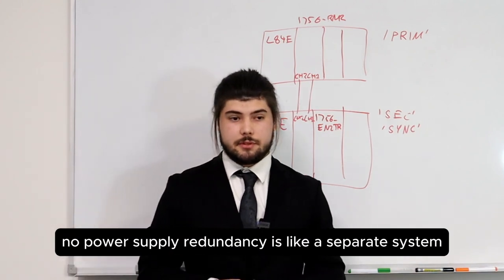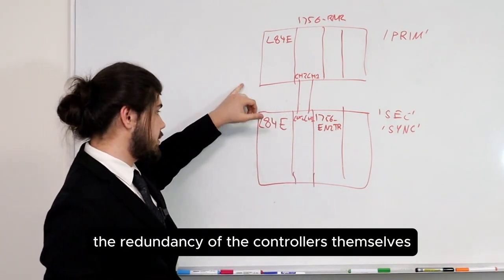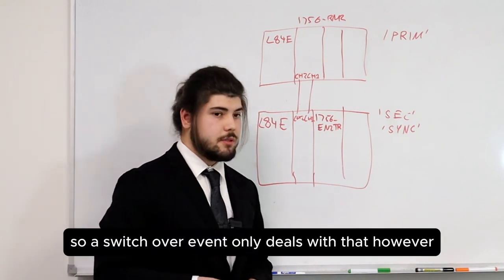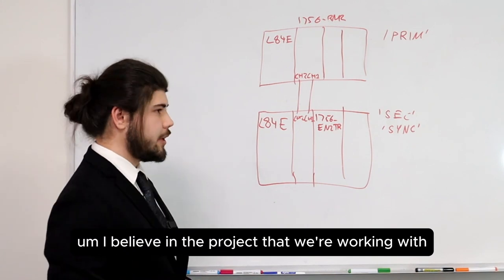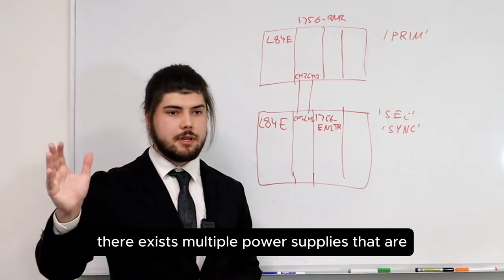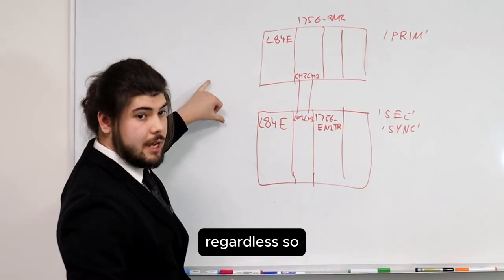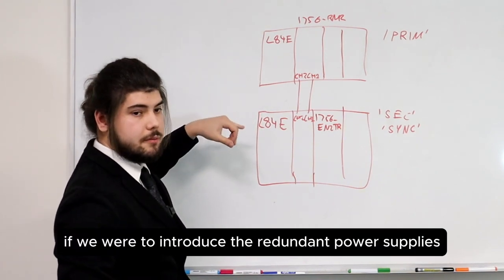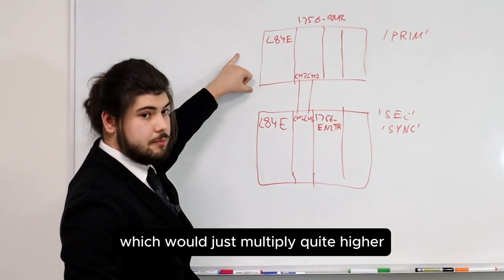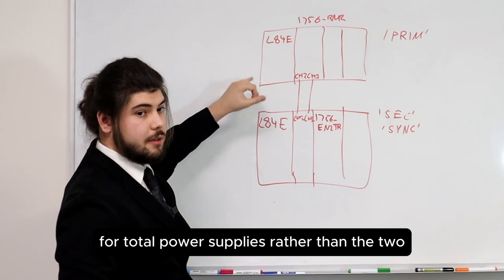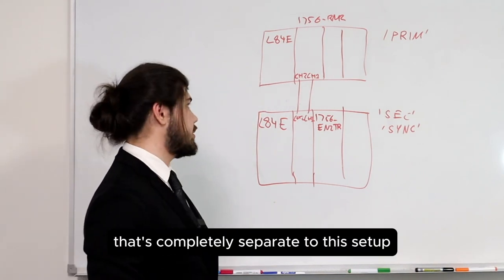Power supply redundancy is a separate system with a separate manual. This presentation is just dealing with redundancy of the controllers themselves. A switchover event only deals with that. In the project we're working with, there exist multiple power supplies supplying both PLCs and both racks separately. If redundant power supplies were introduced, you'd have two power supplies per PLC — four total rather than the two which already exist and are in themselves redundant. That's completely separate to this setup.